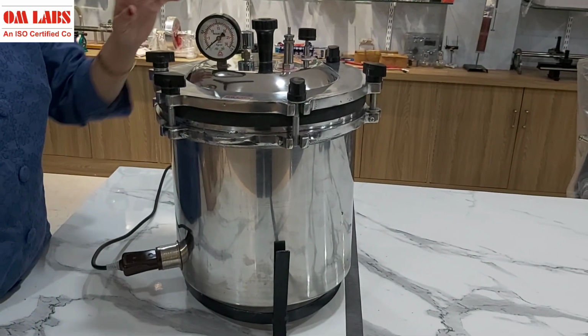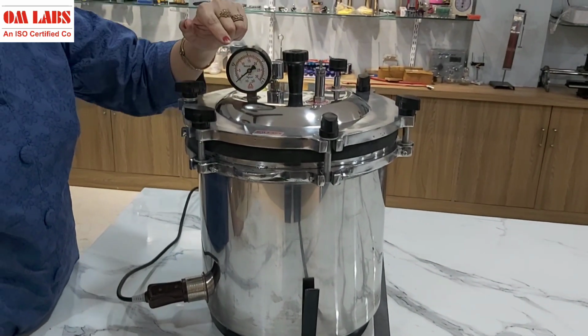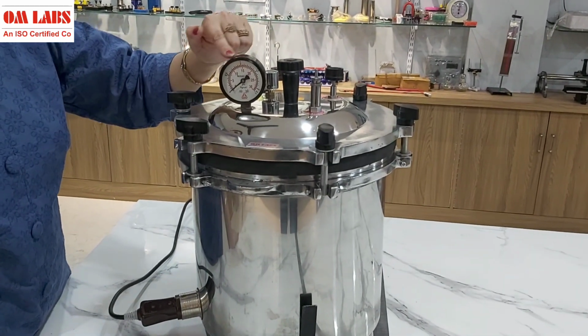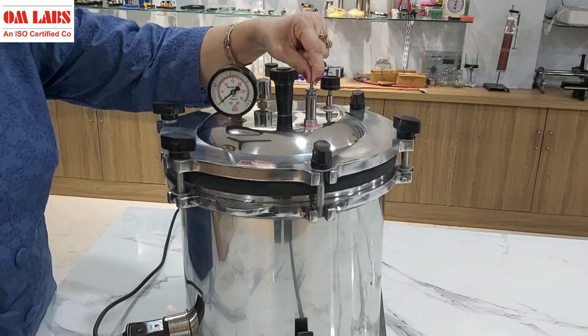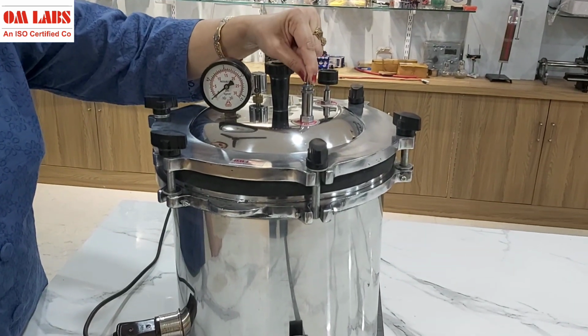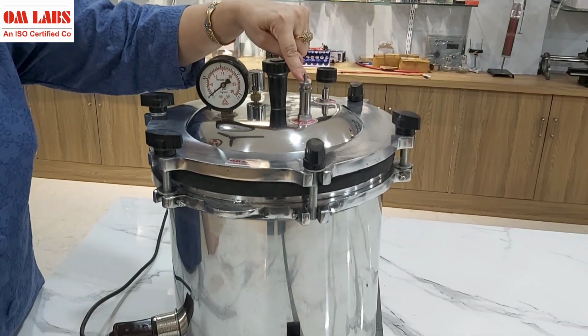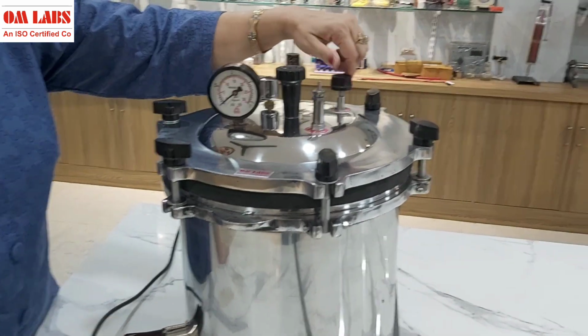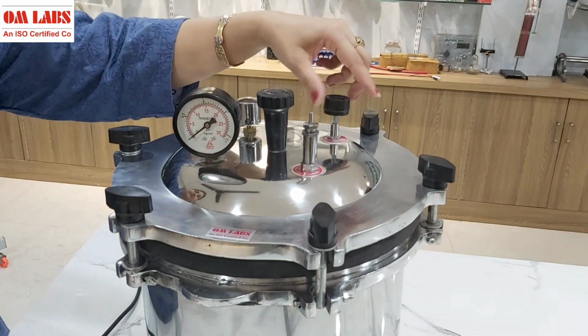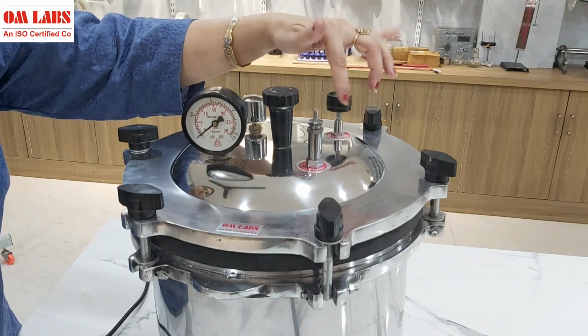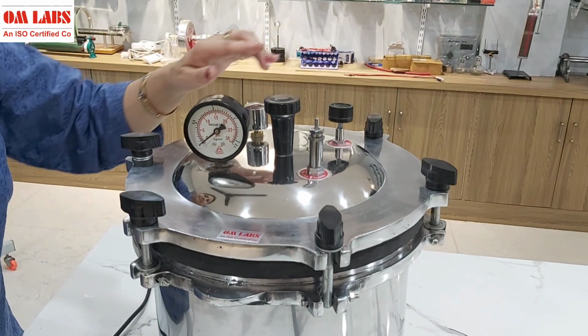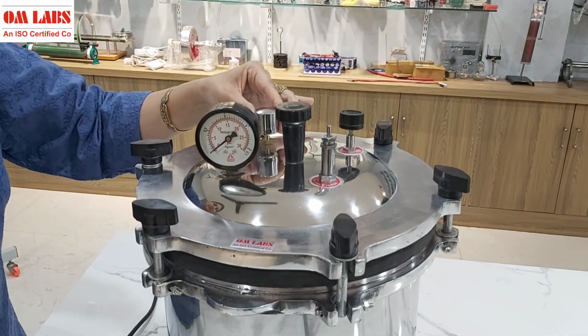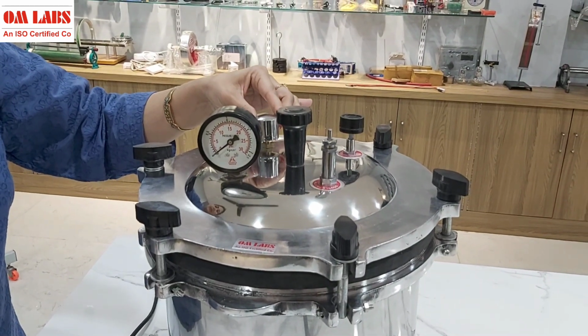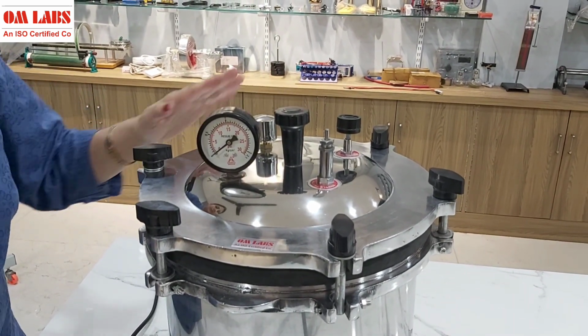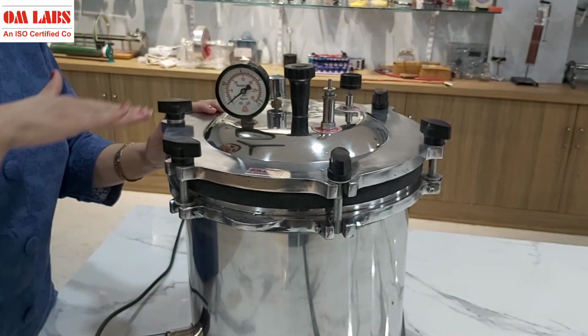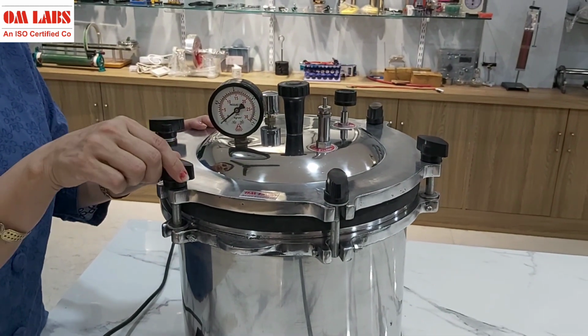This is the top of the autoclave which has different parts on it. This is the pressure valve which indicates the pressure generated inside the autoclave. This is the safety valve which provides safety and prevents bursting of the autoclave. This is a simple screw valve which simply helps to release vapors from the autoclave. This is similar to the whistle in a pressure cooker. It releases the pressure developed. So these are the major parts on the lid, including these several pairs of nuts on the lid of the autoclave.